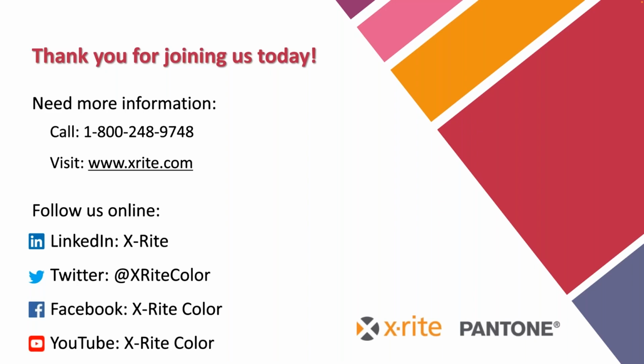So yes, a profile is only valid for 30 days. Once it's expired, the device will actually disable the profile. This will introduce error back onto the device and those measurements. So it's really important for us to re-profile our devices every month, actually every 30 days, just to keep that up to date. That's a good question.